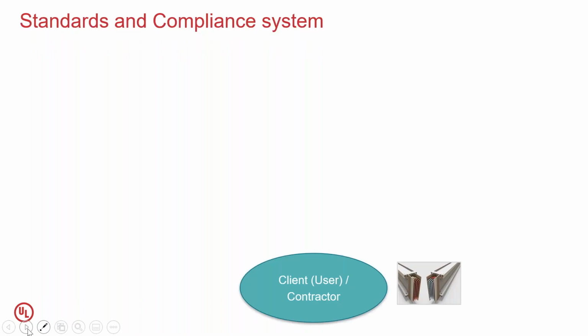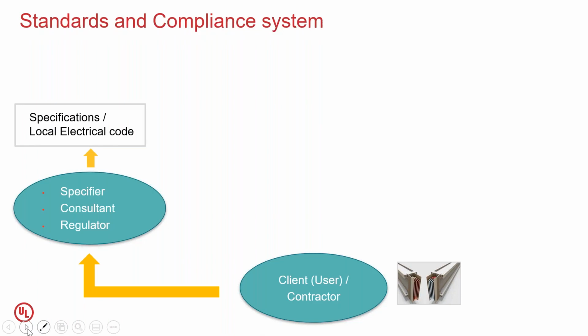To start with, an end user or a contractor or a large buyer or a building owner who wants electrical products to be installed, let's take busways in this case, how does he refer or how is he made to use the standard? Now it all starts with the specifiers or the consultants or the regulators specifying that these products must comply to an international standard or to a national standard. So in this case, the specifier or a consultant very clearly specifies the busways and the busway accessories like the bends, the plug-in units, and all the related accessories. They will mention in their specification that these products must be in compliance to a particular IEC standard. Now, how does it get specified? It could be specified in a specification, or it could be a part of an electrical code, which is very prevalent in Europe and North America.